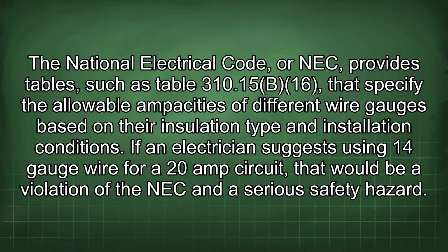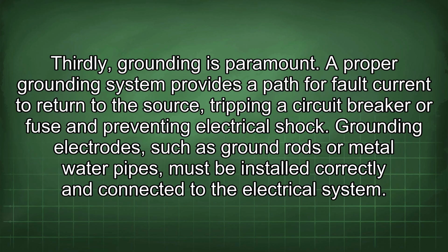The National Electrical Code, or NEC, provides tables such as Table 310.15(B)(16) that specify the allowable ampacities of different wire gauges based on their insulation type and installation conditions. If an electrician suggests using 14-gauge wire for a 20-amp circuit, that would be a violation of the NEC and a serious safety hazard. Thirdly, grounding is paramount.